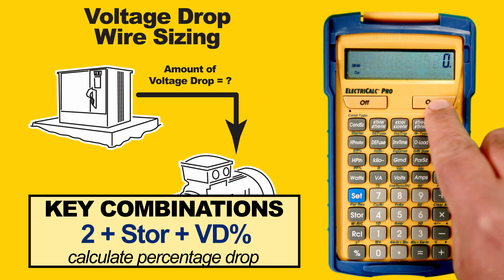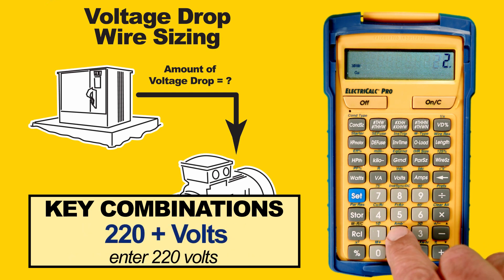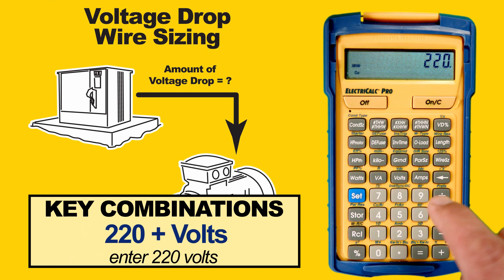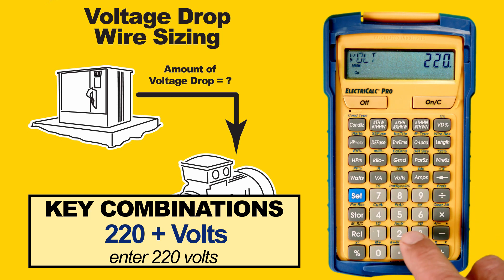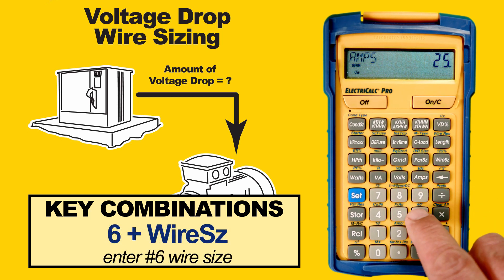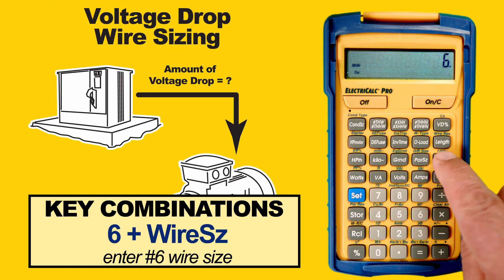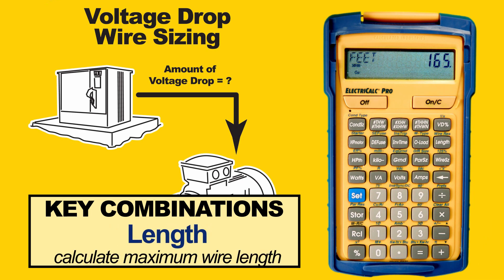We have 220 volts, 25 amps, and we're going to use number 6 Romex. So we enter 220, then press the Volts key. Enter 25, then press the Amp key. Then enter 6 and press Wire Size. Pressing Length will calculate the maximum length it can go.